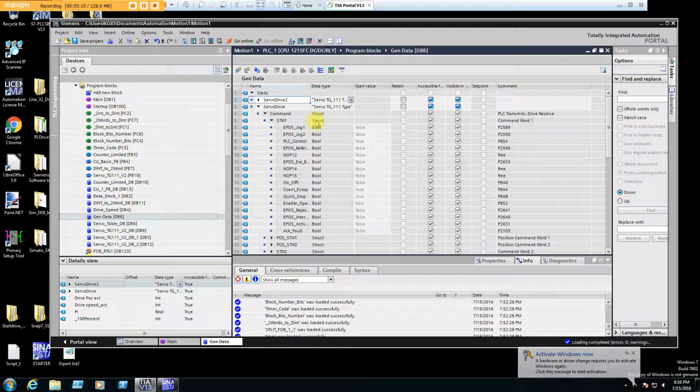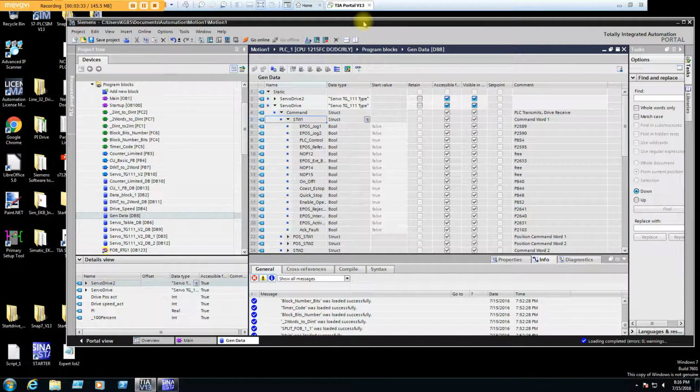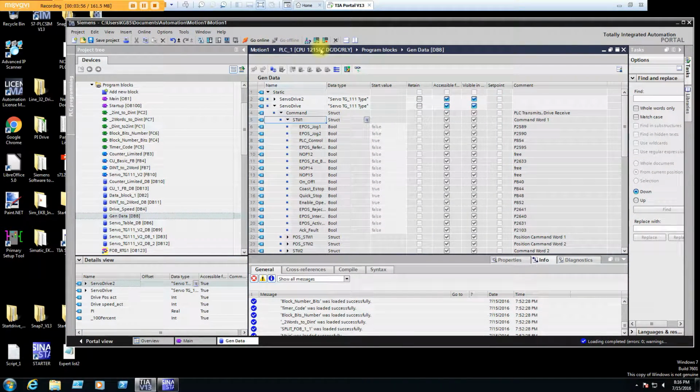But one of the places it shows up, if you're just in the Siemens world, is in the way data shows up. If you're trying to do things in bools and push them into a word, something the drive does all the time, and then in the PLC you're looking at it, it is high byte first. It's Big Endian. So that's no big deal, except when you're looking at it, you have to remember the way the high byte and the low byte show up. It is not 100% intuitive if you're not aware of the way the data is getting there through Profinet or Profibus or Modbus or whatever you're using. So I just wanted to show that.